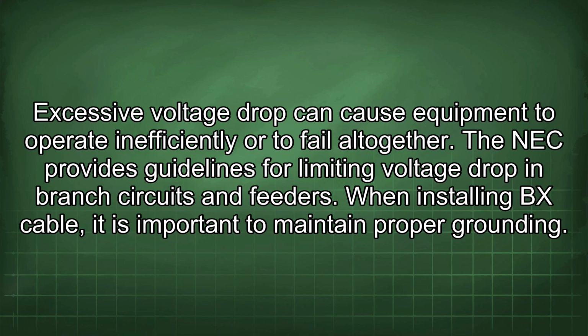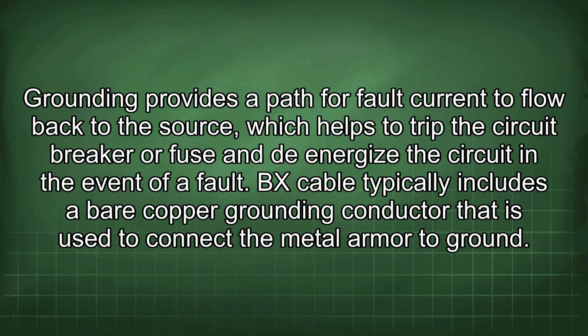When installing BX cable, it is important to maintain proper grounding. Grounding provides a path for fault current to flow back to the source, which helps to trip the circuit breaker or fuse and de-energize the circuit in the event of a fault. BX cable typically includes a bare copper grounding conductor that is used to connect the metal armor to ground.